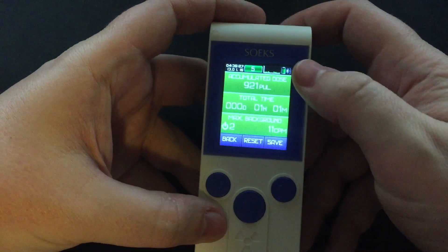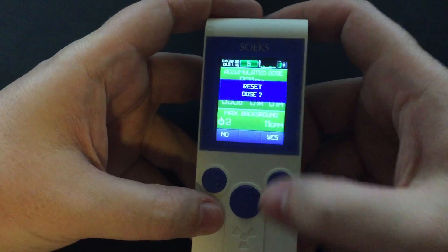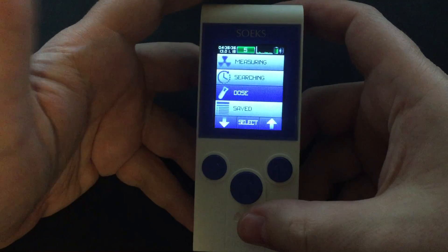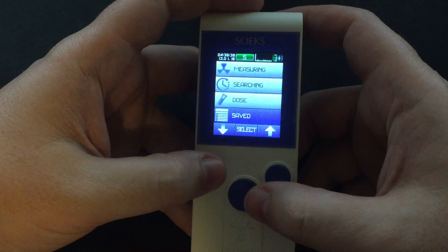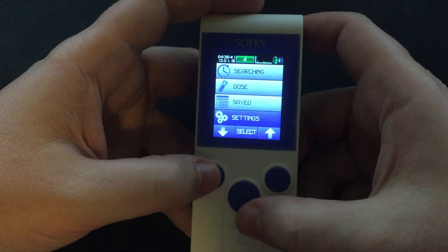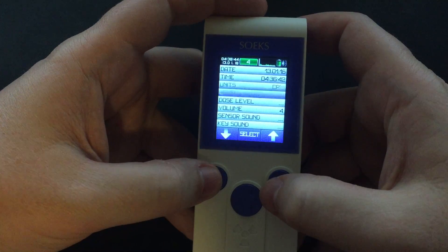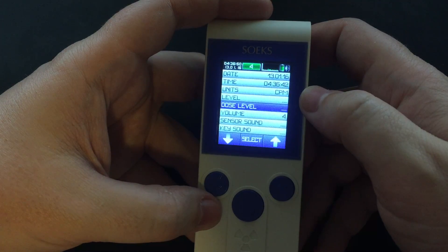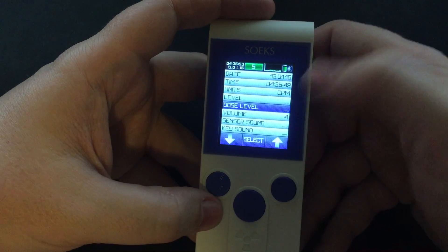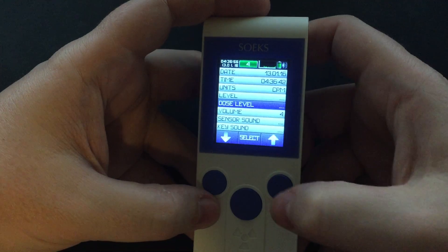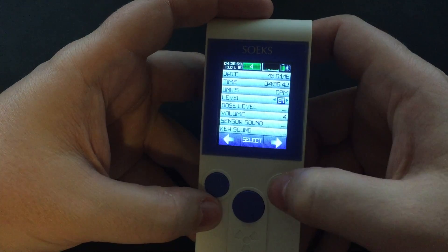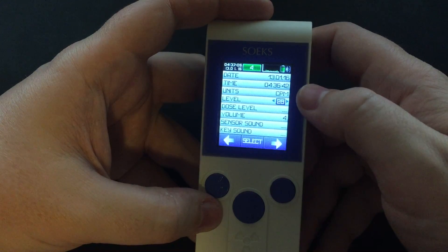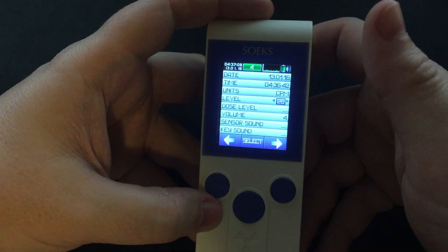Your dose rate is your accumulated dose rate over time. It's easy to reset, but if you just leave it on, I'll explain in a minute. Save stores any dose rates you've seen. If you go into settings and dose level, once you hit this dose level it will alarm — and it can get annoying, especially if you forget to frequently reset your dose level. This level is a warning level. I usually set it about three to three and a half times normal background. If it gets up to the high, it starts beeping — like hey, you want to look at this, something's going on.